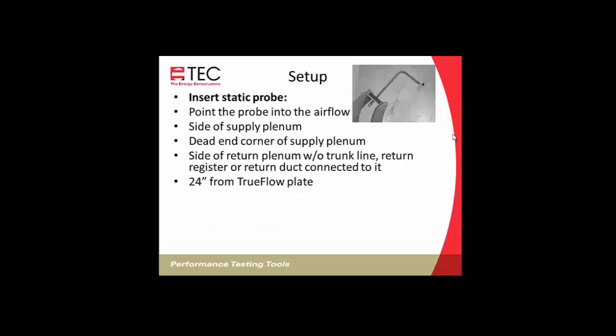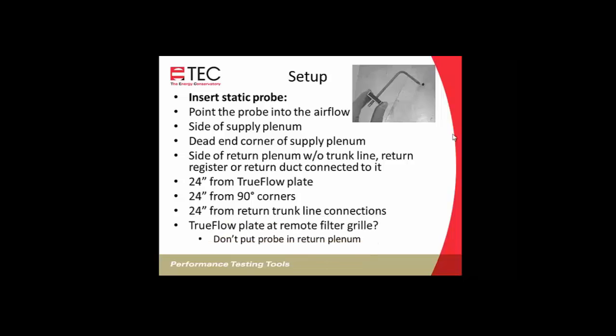We want that static pressure probe to be at least 24 inches from the TrueFlow plate, 24 inches from a 90-degree corner, and 24 inches from any return trunk line connections. And also, if we're installing our TrueFlow plate at a remote filter location, then we don't want the static pressure probe going in the return plenum.